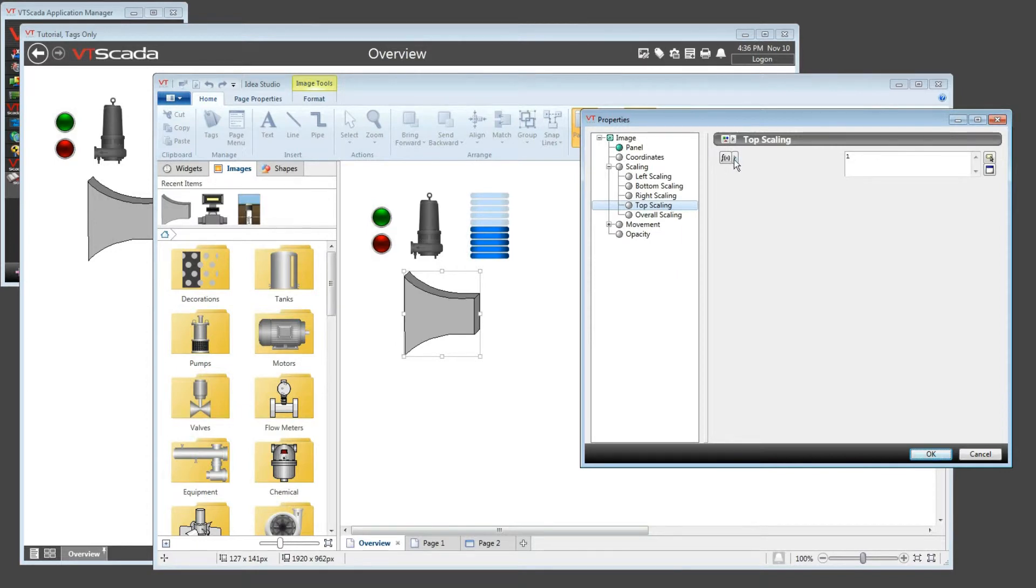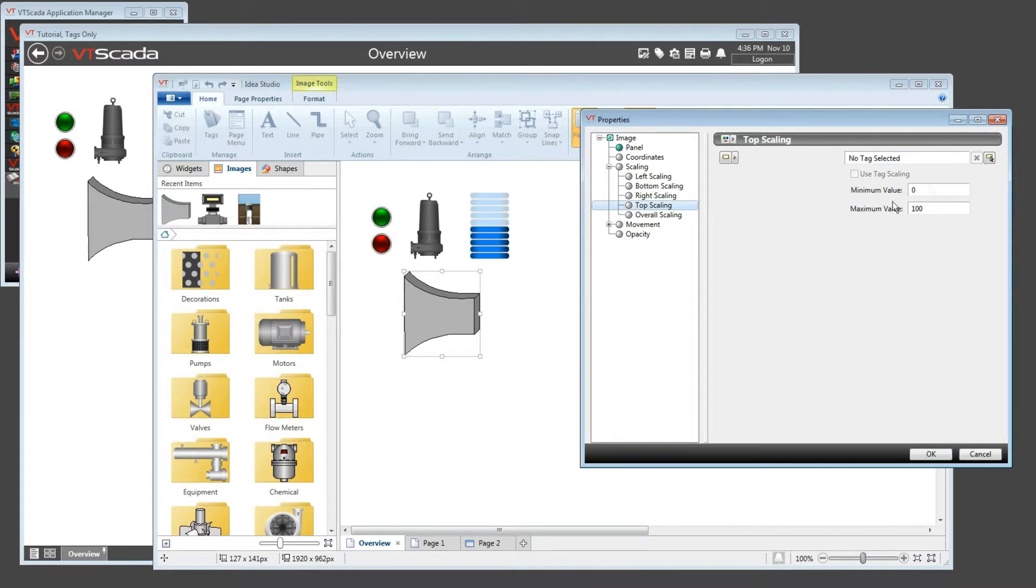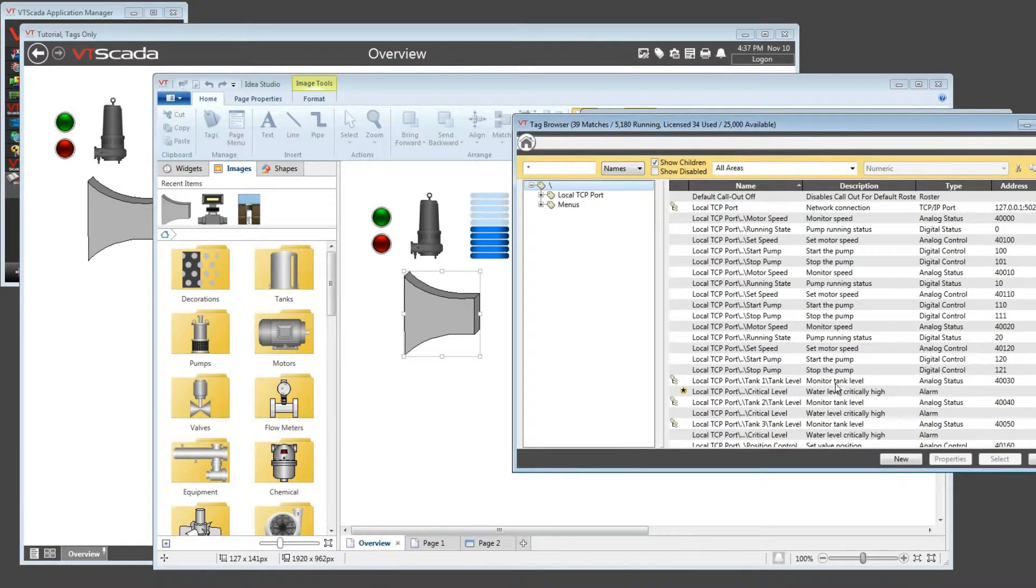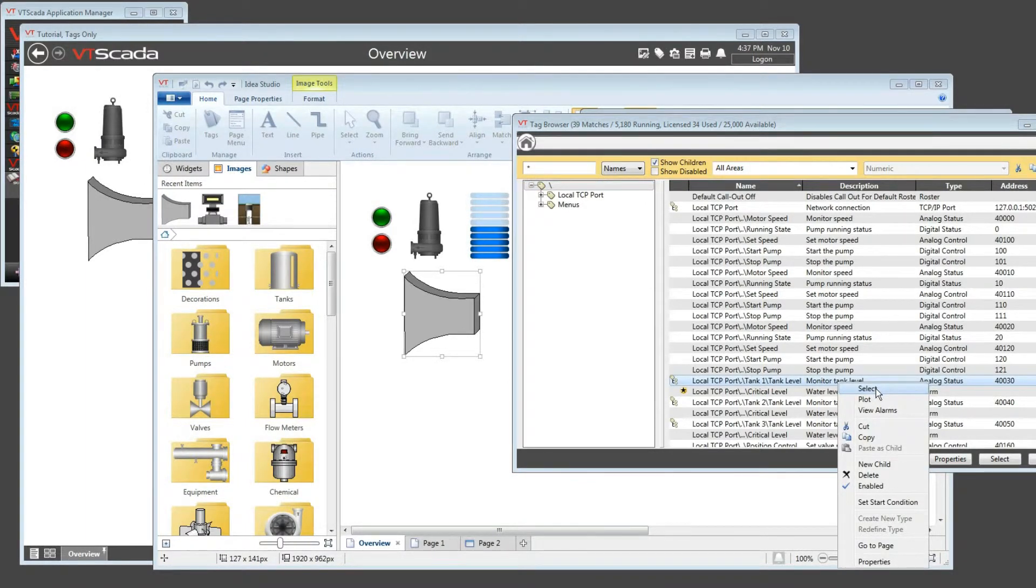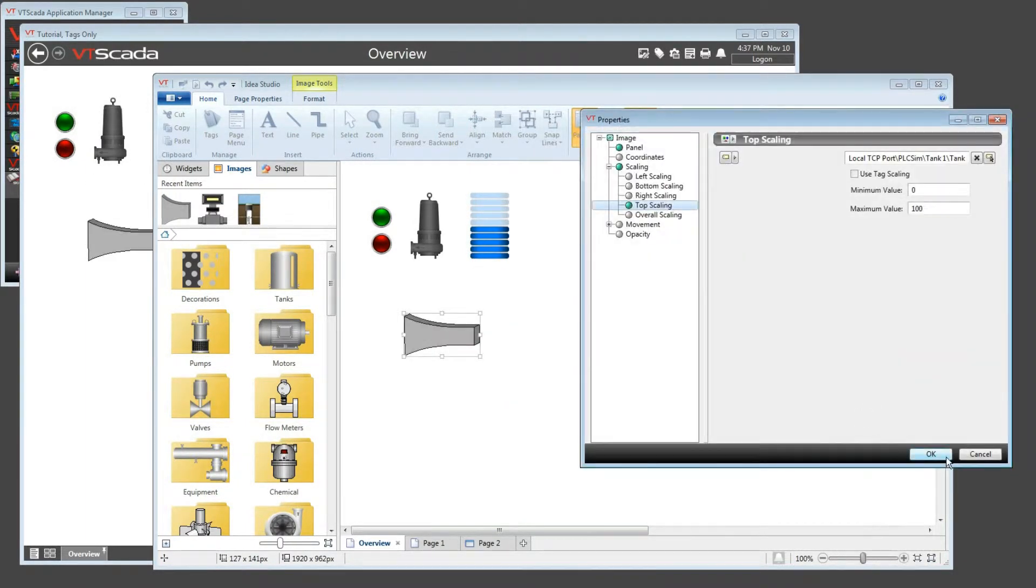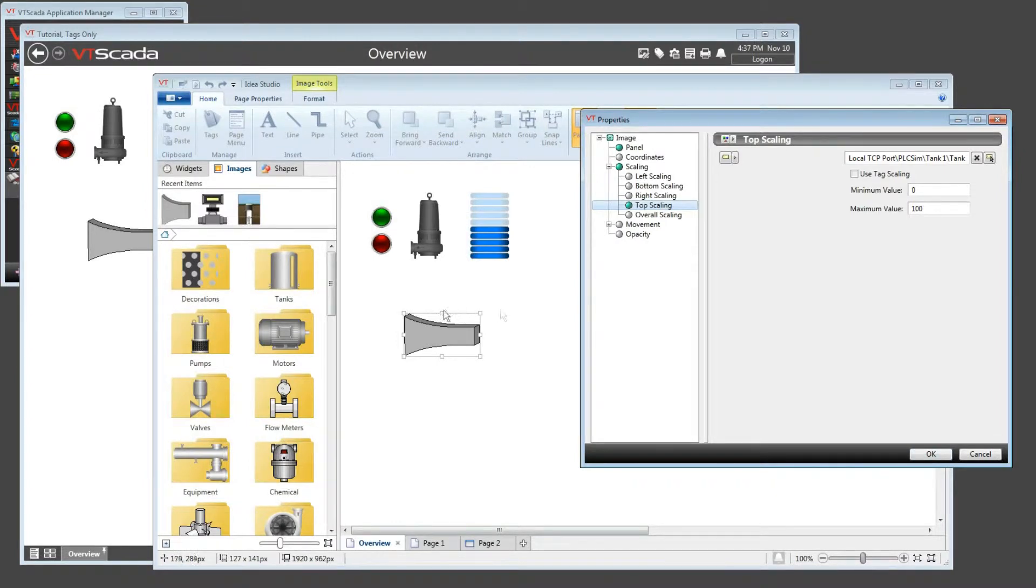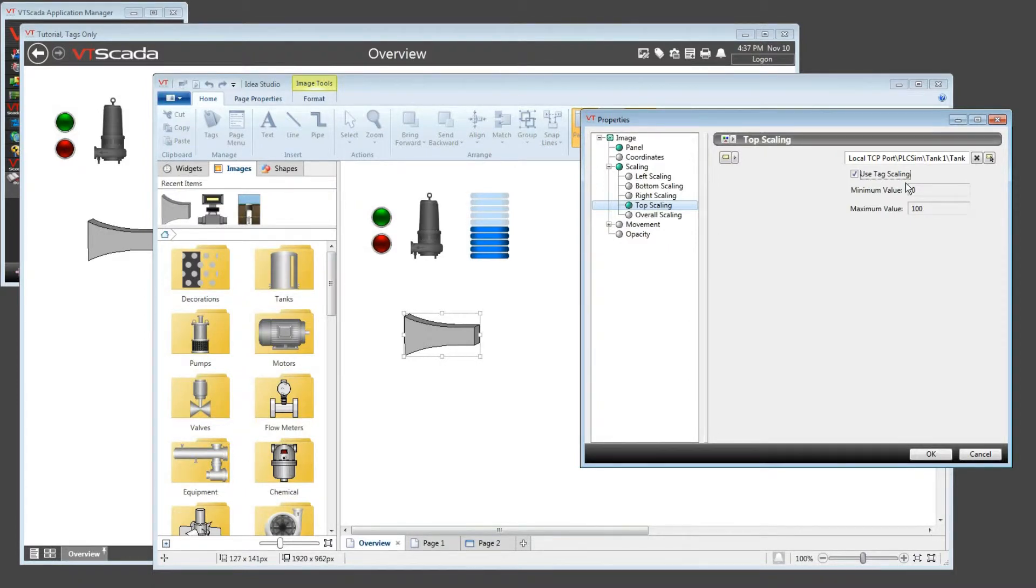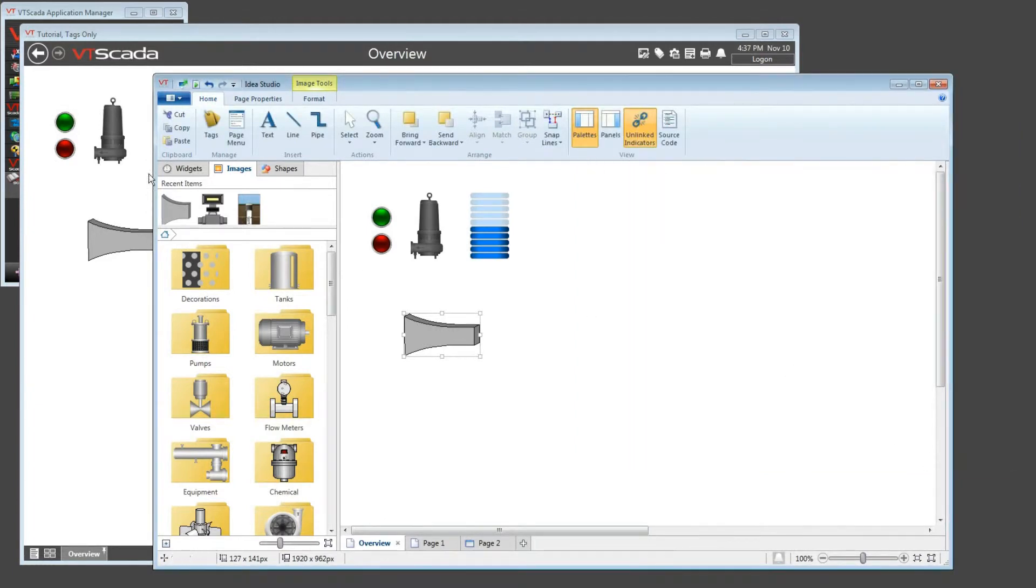I'm going to choose the top scaling, and now I'm going to use, instead of a simple value of one, I'm going to find a tag value. And here I'm going to select the tank level. So I'll select the tank level, and the image immediately squishes. I'm going to use the tag scaling. Now, as the tag goes from its lowest value to its highest, the image will go from absolutely flat up to its full size.